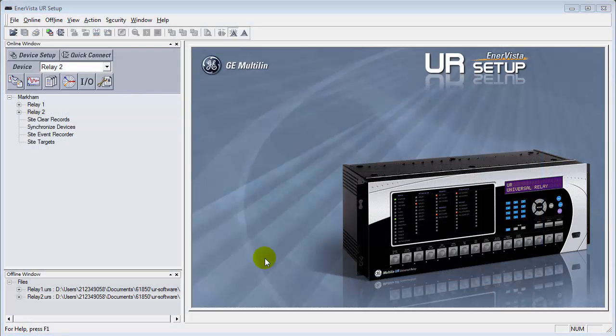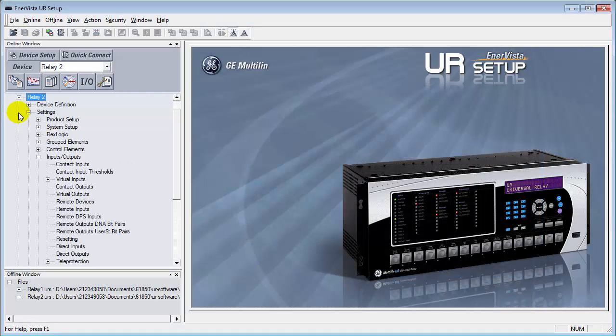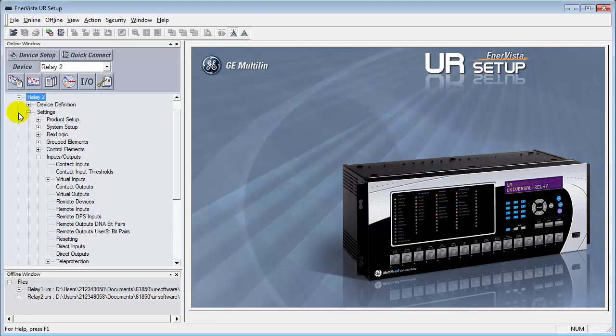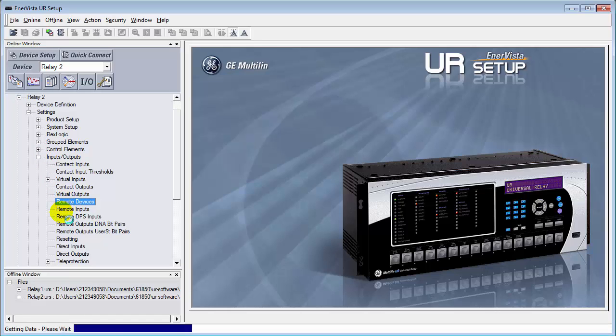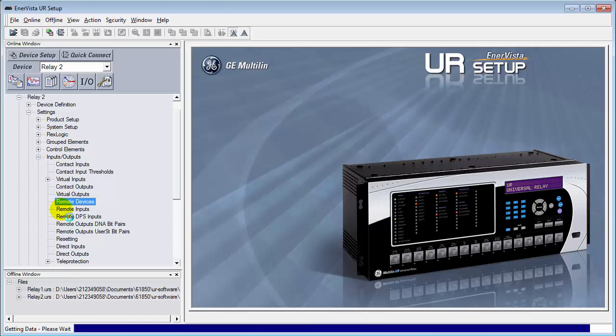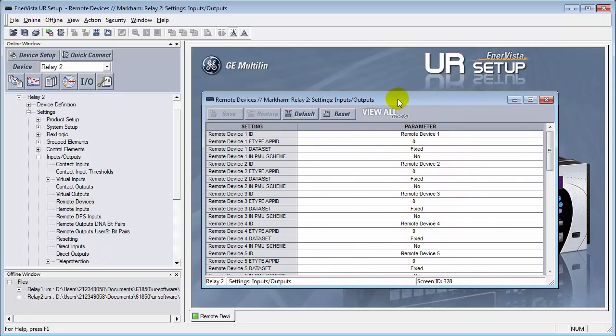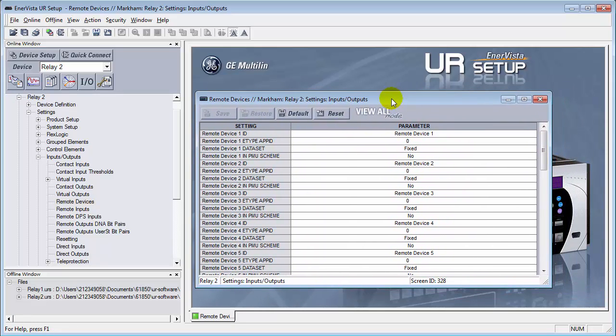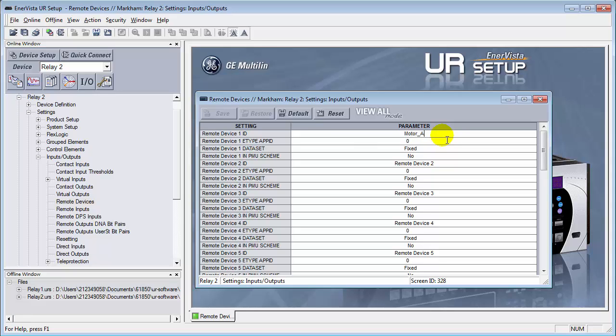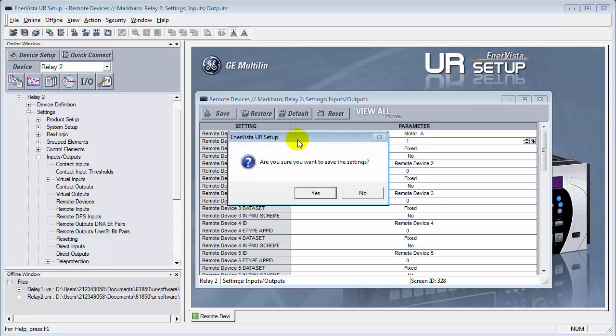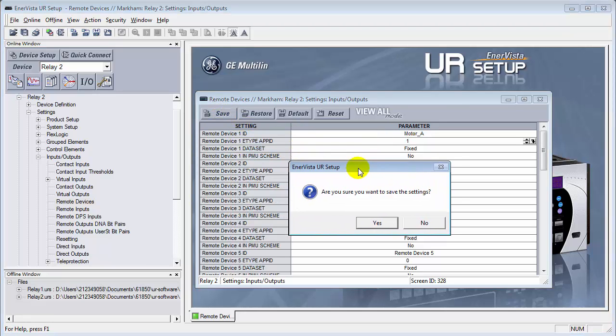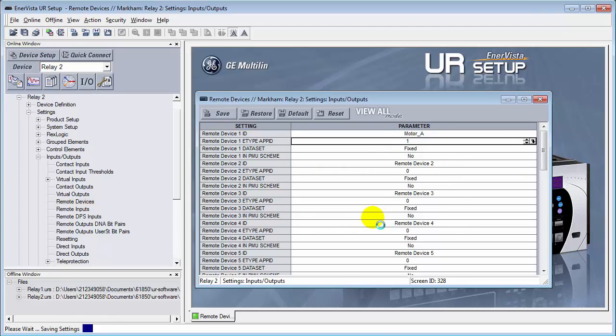Now I'll configure relay number two to be the subscriber. The first thing that we need to do is we need to go down into the settings section under inputs and outputs. And the very first thing that we need to go to is our remote devices. We'll open up remote devices. This is where we have to list the goose messages that are remote to us. So the goose message that we were looking for from relay one is a message called motor_a. Make sure we get the E type application ID, which in this case was one. And this will now, we can save this. Hit yes.